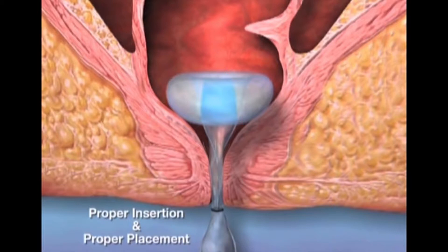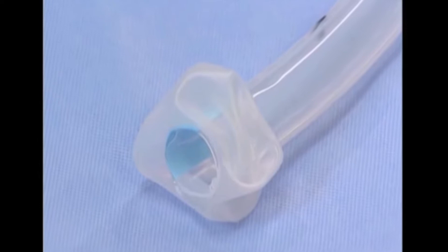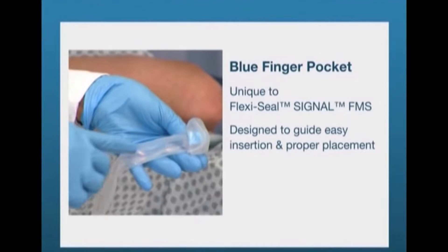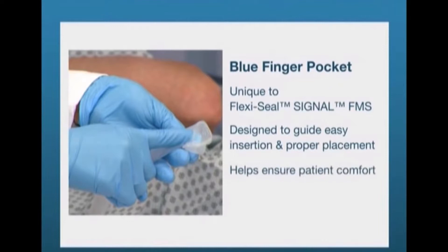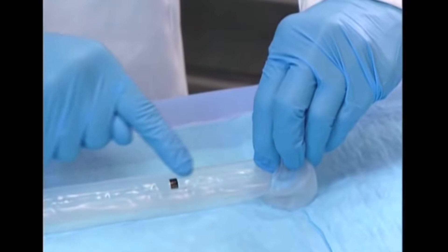In place, the drainage tube collapses to an 8 mm diameter, minimizing the impact on sphincter tone. The retention balloon has a blue finger pocket that is easy to locate and designed for simple finger insertion. This is a unique feature available only on FlexiSeal Signal FMS devices, designed to guide easy insertion and confirm proper device placement. You can locate the finger pocket by moving your finger along the irrigation line starting from the blue irrigation port up to the balloon. The finger pocket is located above the position indicator line.